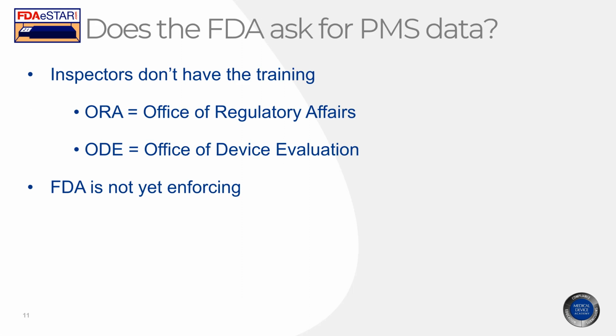So does the FDA ask for any post-market surveillance data? I mean, we did talk about use errors in usability, and we did talk about cybersecurity, but does the FDA during an inspection ever ask for post-market surveillance data? The answer is no. I have never heard an FDA inspector asking for post-market surveillance data other than complaints and MDRs. That's all they ask for. That's the first thing they go to: CAPA, complaints, MDRs, and that's where most of your 483s are issued. We don't have inspectors looking at post-market surveillance procedures and saying you're not following 821 in the standard, and they're not writing up 483s for your PMCF studies and saying you should be doing things differently.